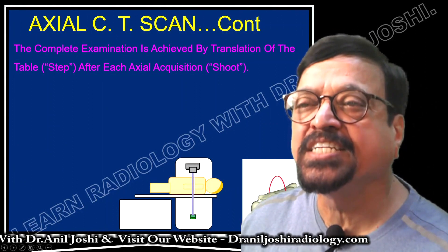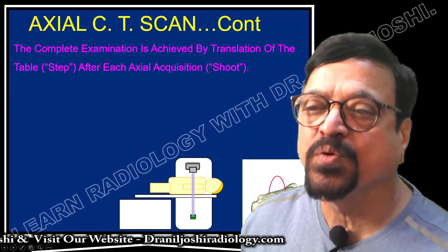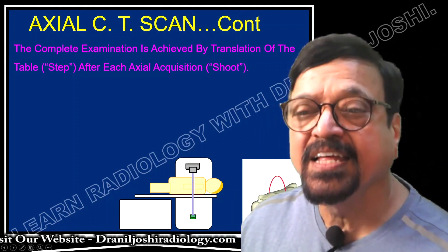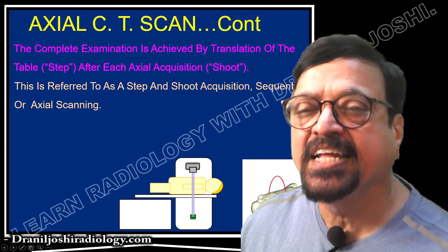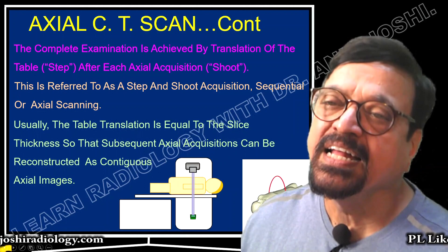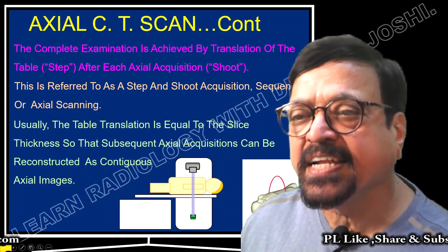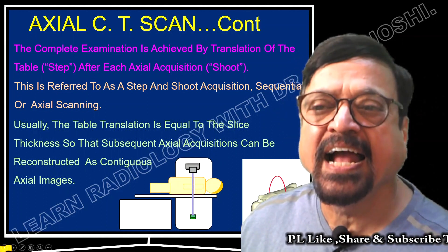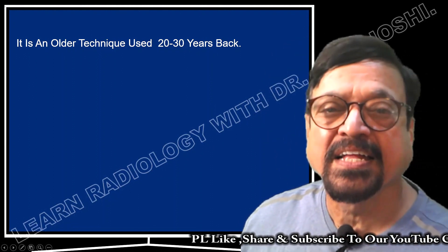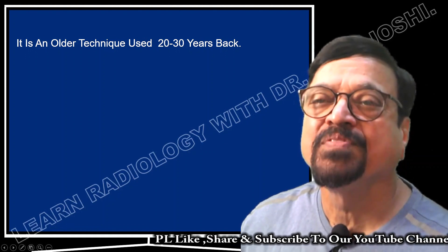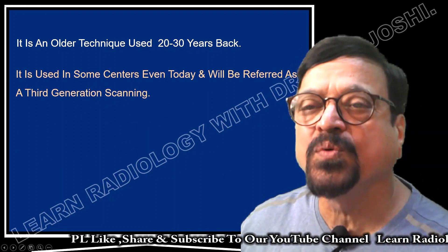The complete examination is achieved by translation of the table step by step after each axial acquisition — referred to as step-and-shoot acquisition, sequential or axial scanning. The table advances by 10 mm at the end of each shoot if taking a 10 mm section. Usually the table translation equals the slice thickness so that subsequent axial sections can be reconstructed as contiguous axial sections. This is an older technique used 20 to 30 years back, still used in some centers, referred to as third generation scanning.